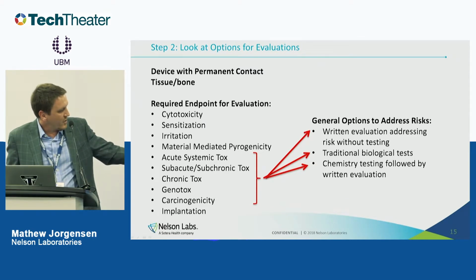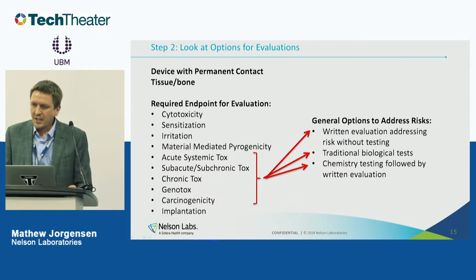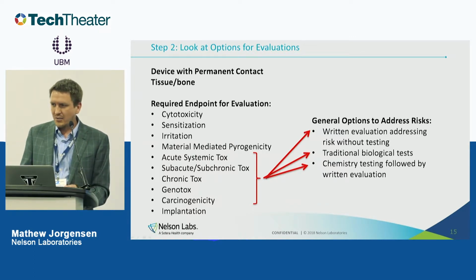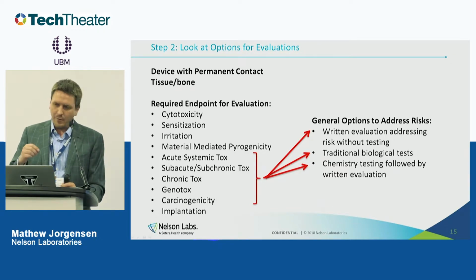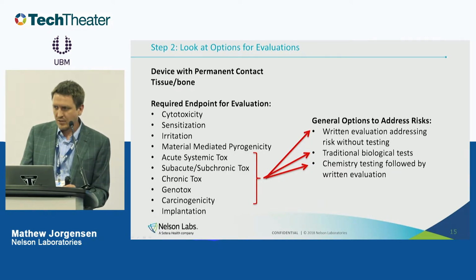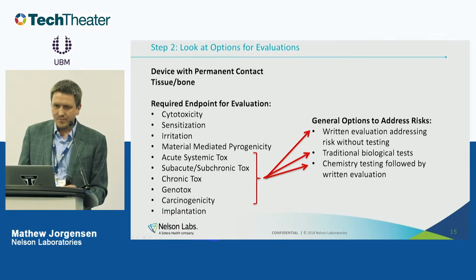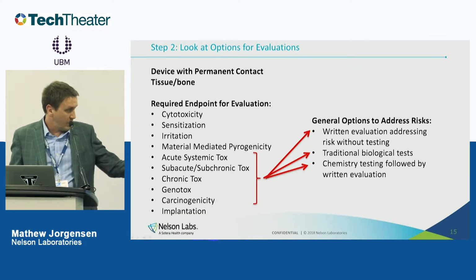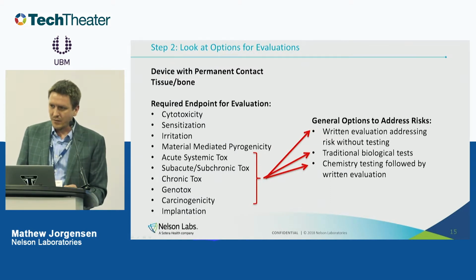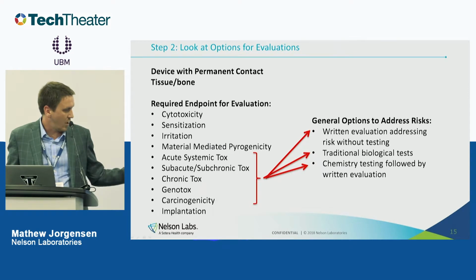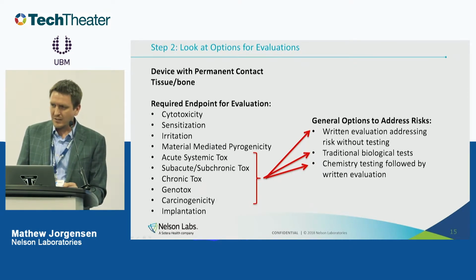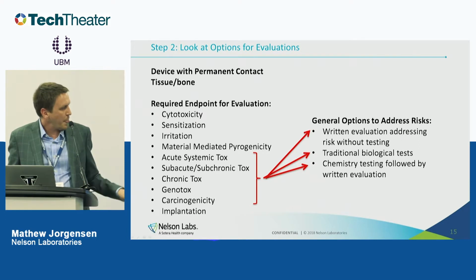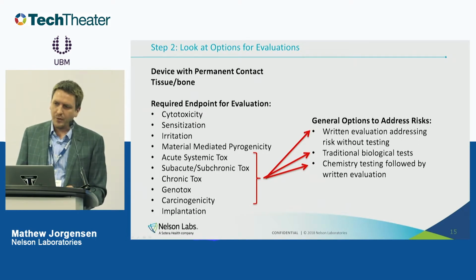For the systemic toxicities, acute systemic, subacute, subchronic, chronic, genotox, and carcinogenicity, you really could do any of those three things to address those endpoints. You could do, and we do this all the time, just a straight pen and paper exercise where you say, we know that this device isn't going to cause these effects because of X, Y, and Z, and this can be really convincing. Of course, you can always do the traditional biocompatibility testing for those, but these are really burdensome tests. A lot of them are very long and expensive, so you want to try to avoid that if at all possible. Or you can do chemistry testing followed by a written evaluation.